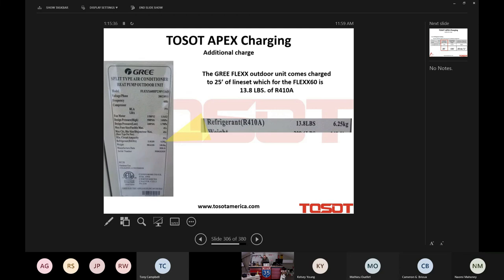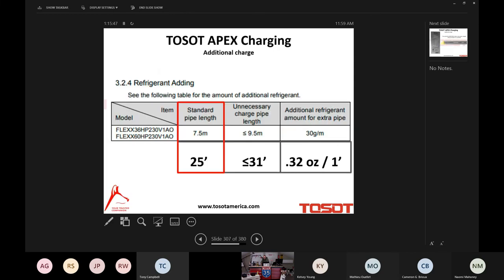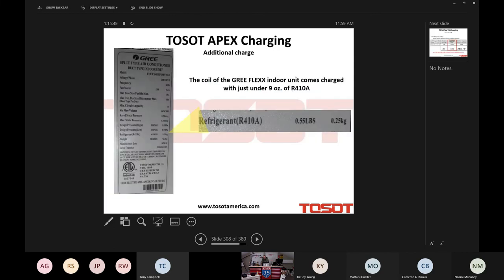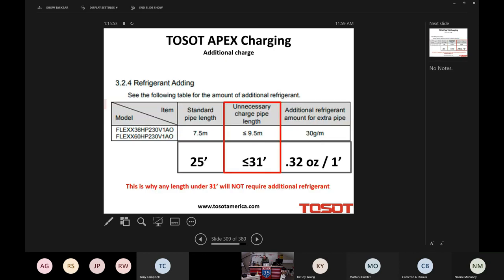The outdoor unit, this is the 4 and 5 ton. The outdoor unit comes pre-charged to 13.8 pounds of R410. That equates to 25 feet. Right, there you go. The indoor unit comes pre-charged to 0.55 pounds. That equates to what? 6 feet, if you do the math here, right?